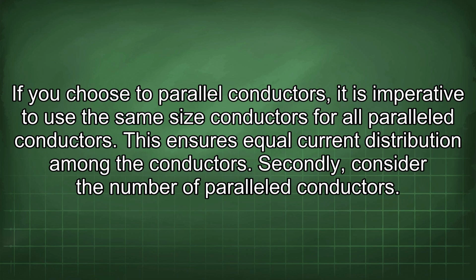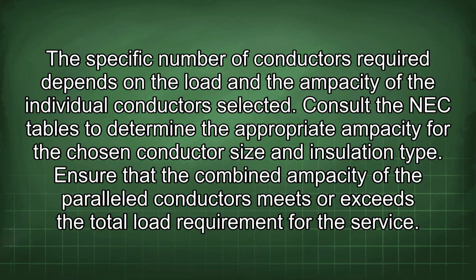Secondly, consider the number of paralleled conductors. The specific number of conductors required depends on the load and the ampacity of the individual conductors selected. Consult the NEC tables to determine the appropriate ampacity for the chosen conductor size and insulation type. Ensure that the combined ampacity of the paralleled conductors meets or exceeds the total load requirement for the service.